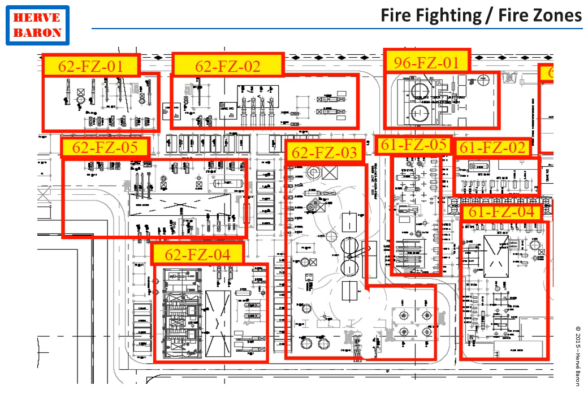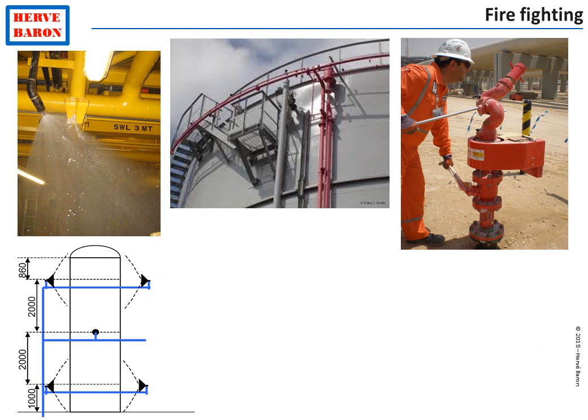Within each fire zone, active and passive fire protection are provided. Active firefighting consists of spraying water on the plant equipment. Spraying water aims at cooling down the equipment so that it will not lose its mechanical strength and collapse. It also aims at absorbing heat from the fire to reduce its intensity. Spraying water can be done by several means.